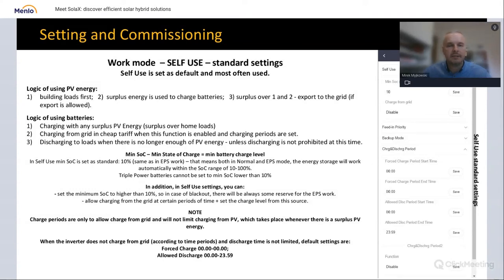The logic of using batteries in that work mode is charging with any surplus PV energy over home loads, no matter the hour — you cannot limit the hours of charging from surplus PV energy; it will charge anytime extra PV energy is detected. It also charges from the grid during cheap tariff hours, but for this you have to enable the function, set the level of charge you want to reach when charging from grid, and set exact periods — from which hour to which hour you declare cheap tariff hours and allow charging from the grid. Discharging from batteries to loads happens when there's no longer enough PV energy.